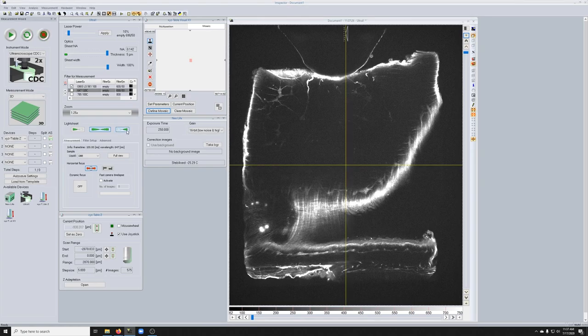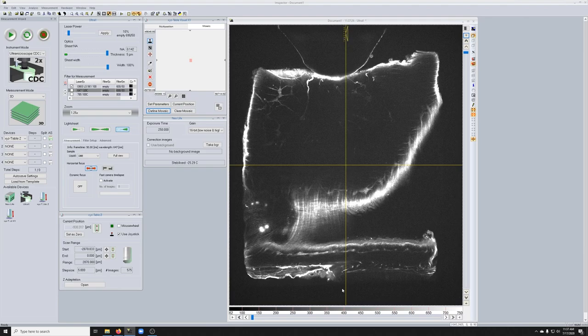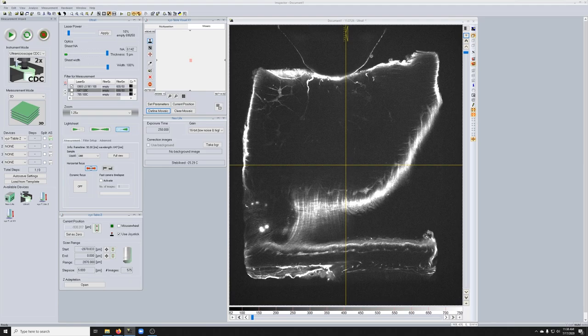Now if you're going to do that, one thing to keep in mind is that it doesn't make any sense, if you're taking images from both sides, to have the horizontal focus, so the place where the waist of the light sheet is at its thinnest in the middle. Why? Because the middle is the part that you're going to interpolate between the two sheets, so you're really wasting the region of higher resolution. What we recommend instead, high resolution in Z, what we recommend instead is to move this to the middle of each quadrant.